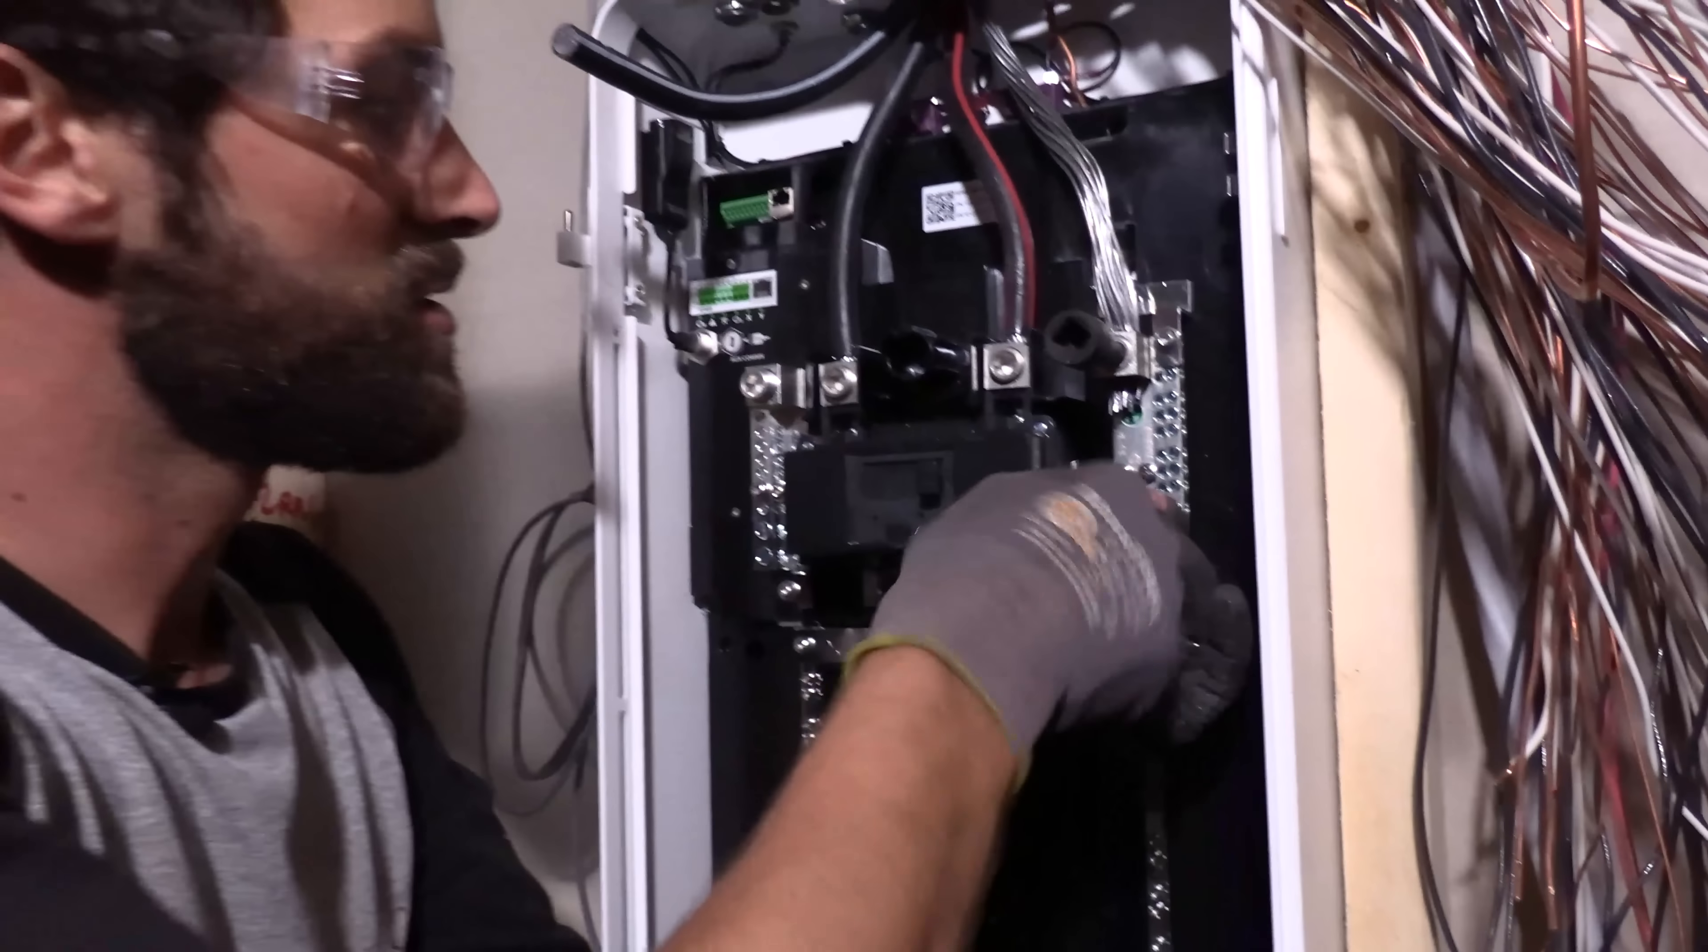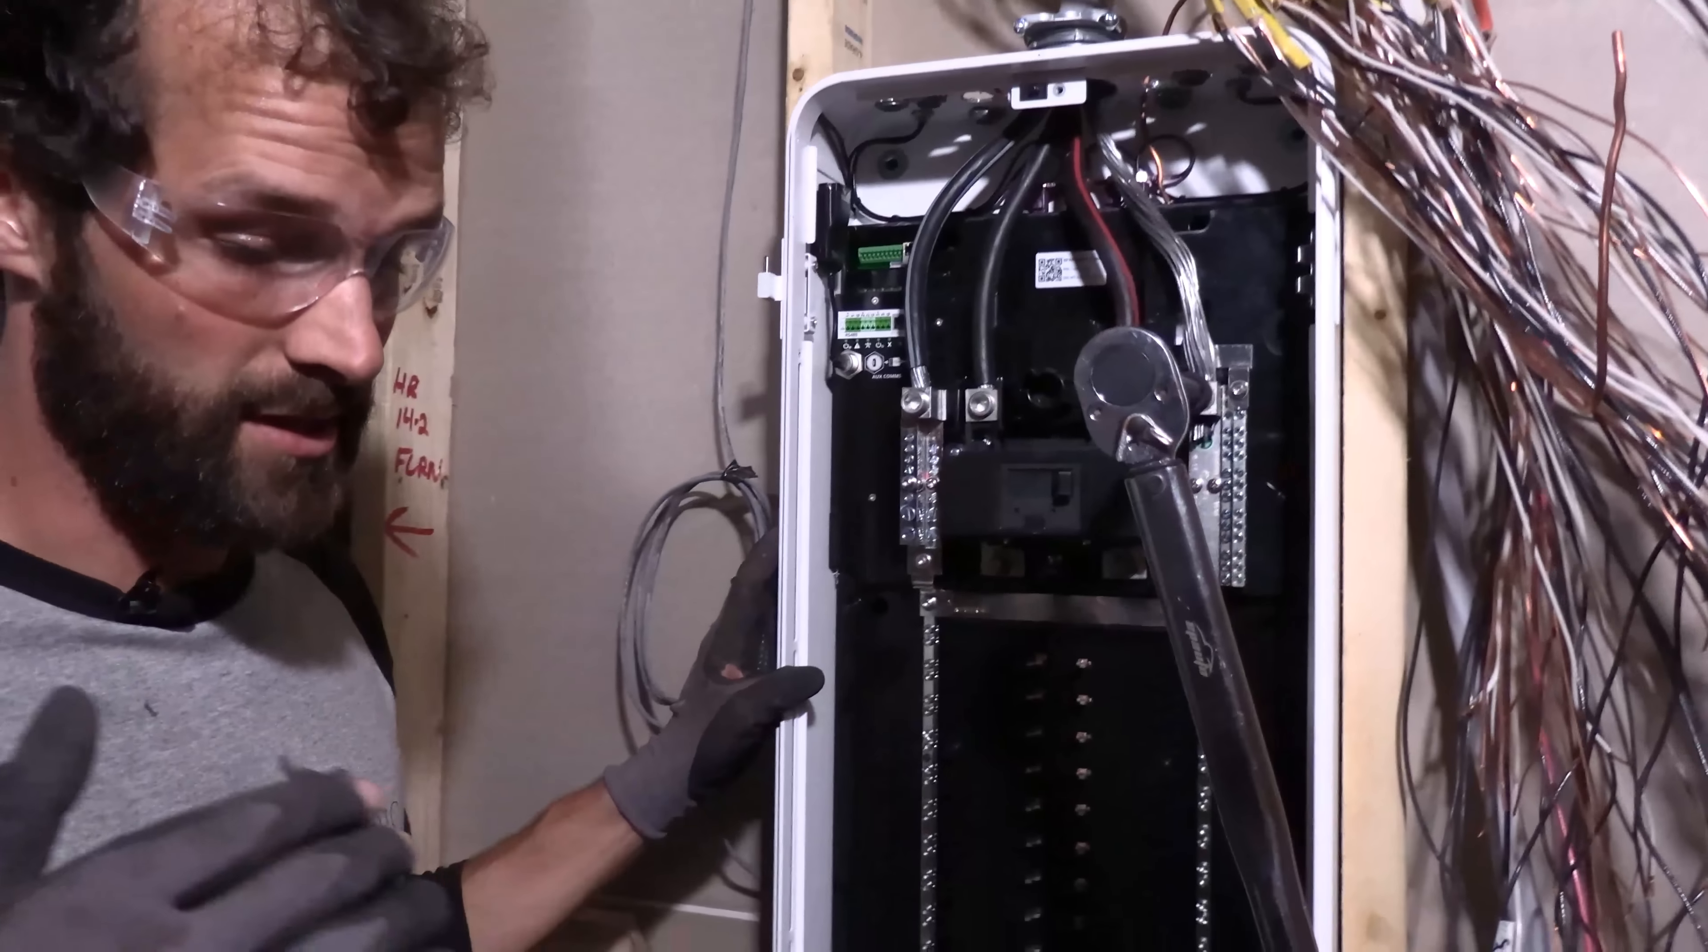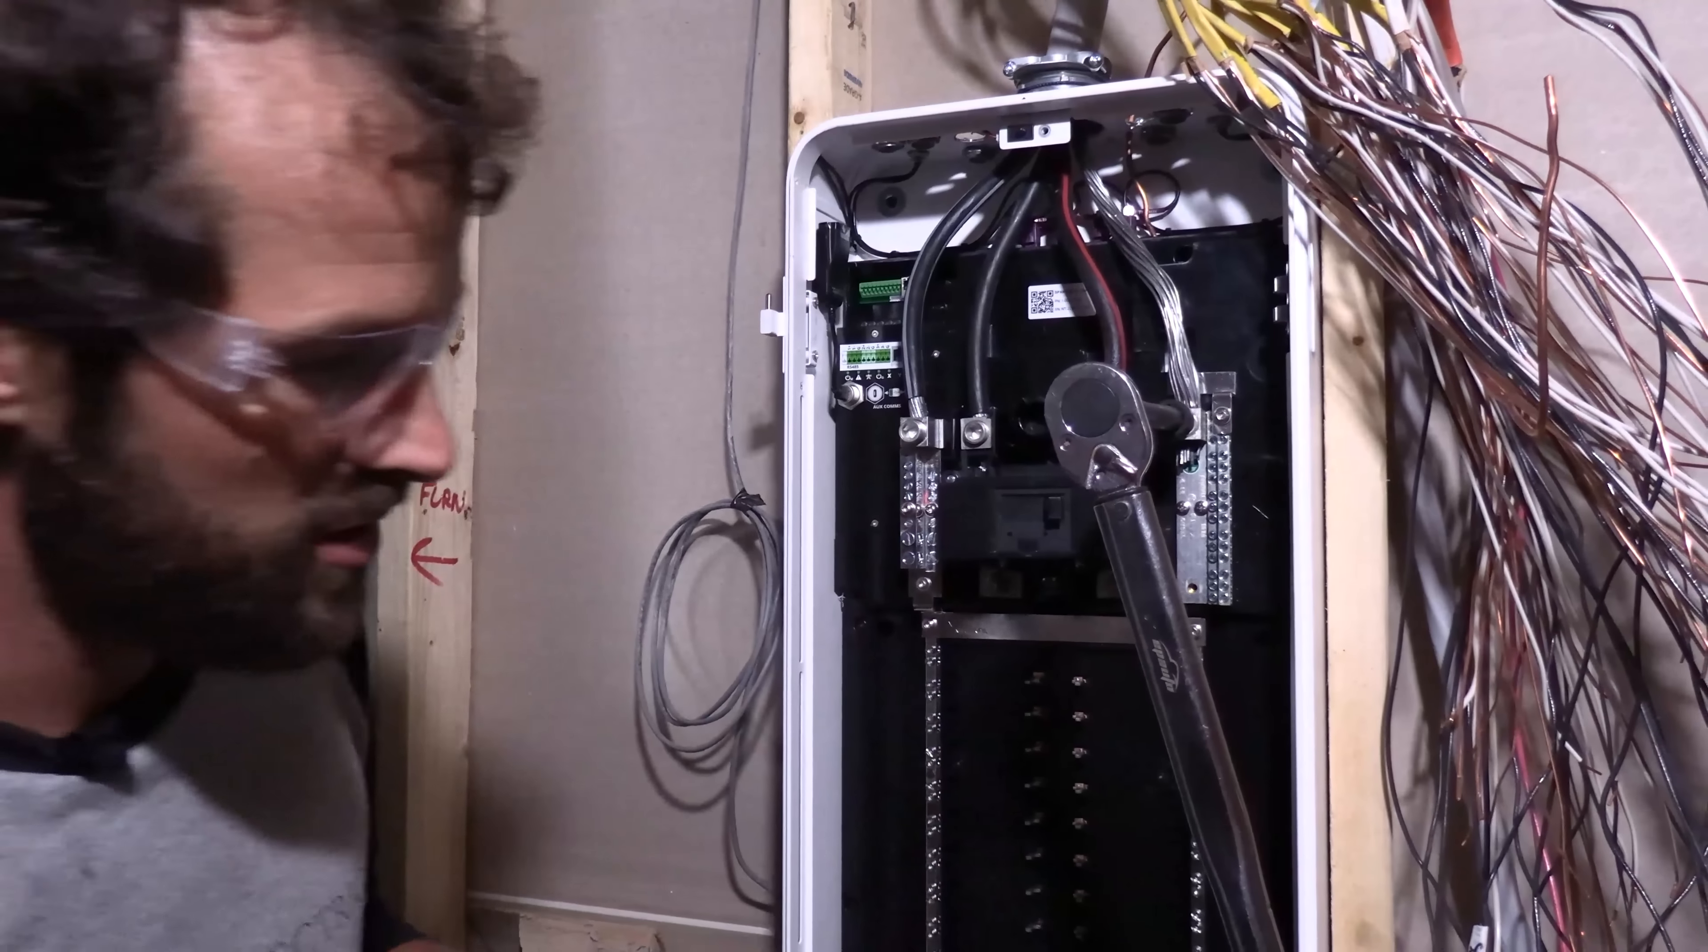They tighten them down all the way, because in transit, those things will rattle free. You'll have a cabinet full of small parts. But it is a little disappointing to have to go through and open them all up. So approved main breakers for span are the QOM 2200VH. This is rated for 22,000 amps of interrupting current. All the torque specifications are inside the main door of the span panel. It's 250 inch pounds for all of these.